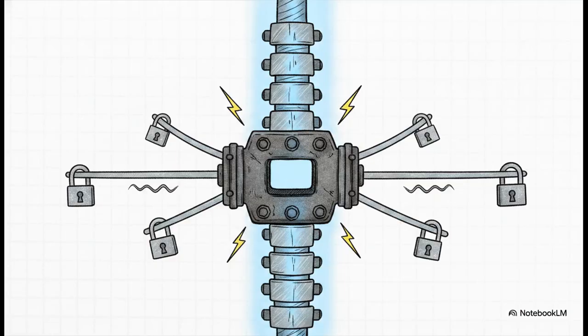So 400 kV gets the tightest leash. Why? Because it's the absolute backbone of the grid. A 5% swing there represents enormous absolute megawatts. So, as a rule of thumb, default to 6% and then double-check specifically for 400 kV because it is the sole exception. Let's test this out with a quick scenario.